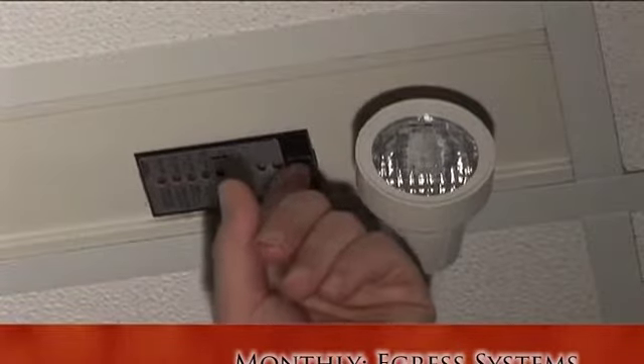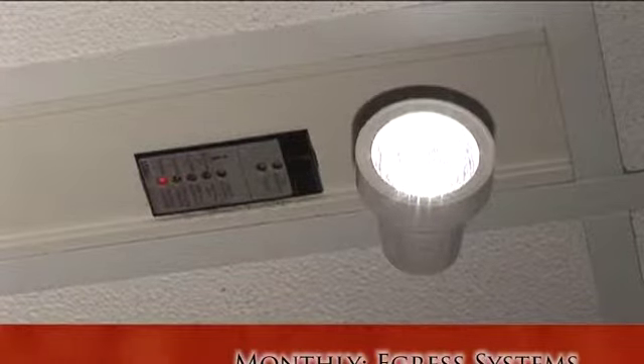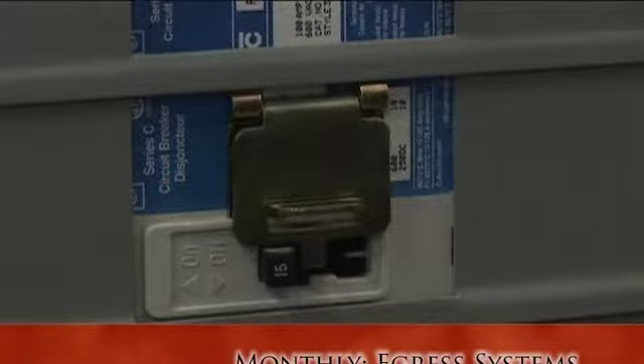Self-contained emergency lighting units must be inspected to ensure that the pilot lights are functioning. Also, test the units to make sure that they'll function when the main power goes out. Testing can be done on each unit or by the main breaker panel.